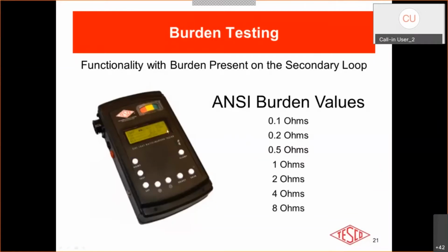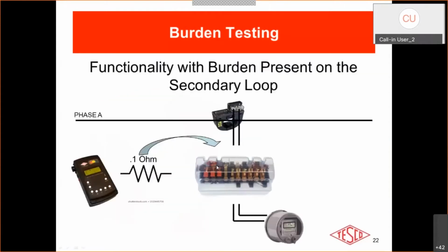So burden test units such as our 1047 shown here utilize a series of high accuracy burdens internally. The burdens being a combination of resistance and impedance. The values set forth by ANSI and IEEE are 0.1, 0.2, 0.5, 1, 2, 4, and 8 ohms. So during a burden test, the test unit simply applies additional burden into the secondary of the CT, and takes a measurement of the secondary current prior to the additional burden applied and then afterwards.